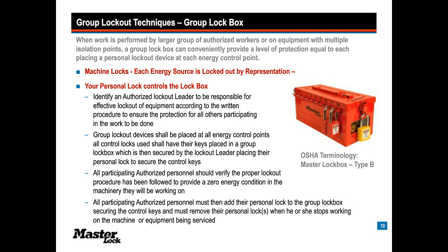If I know that I'm leaving for the day, if I know that I'm leaving because my work here is done, I will remove my lock at that time so that as the work is fully wrapped up, my locks are not behind when I'm not paying attention to the job anymore. That makes for an emergency removal requirement that can complicate the process as well. So personal locks should be on the box only for the duration of personal exposure.